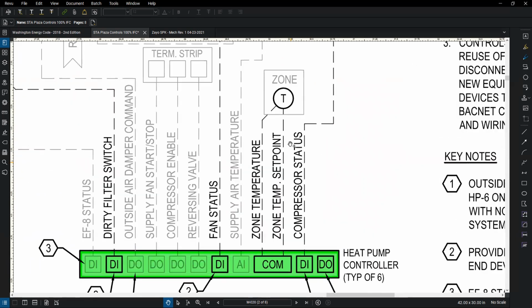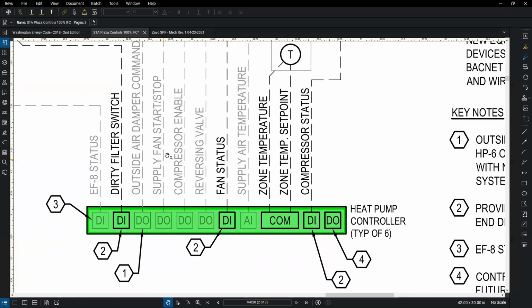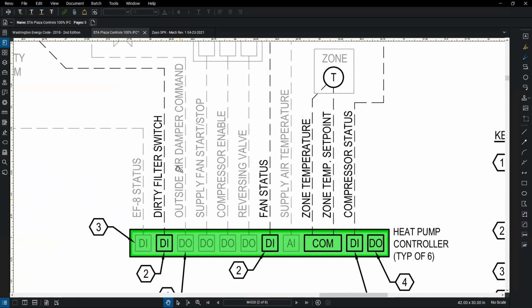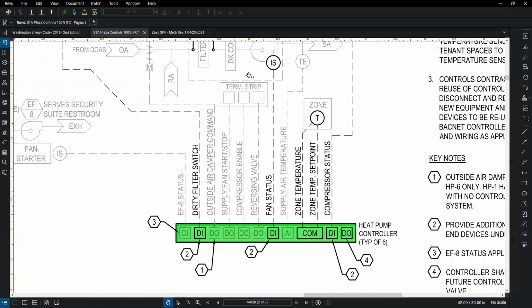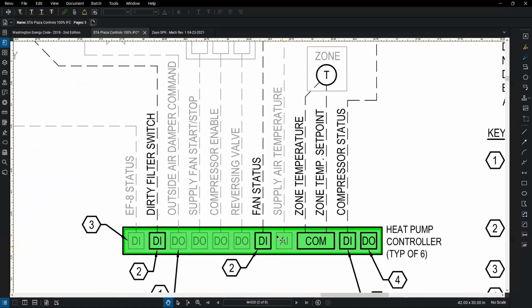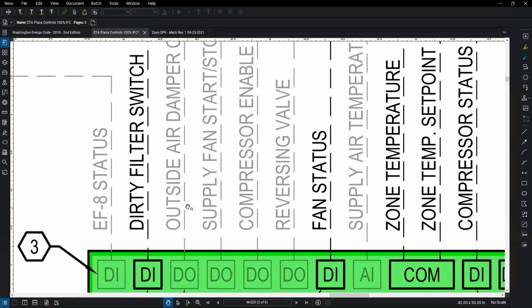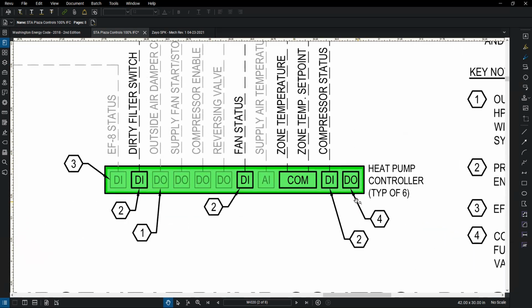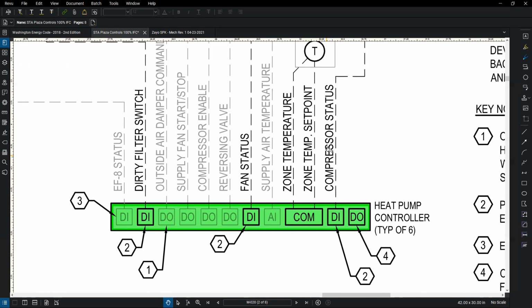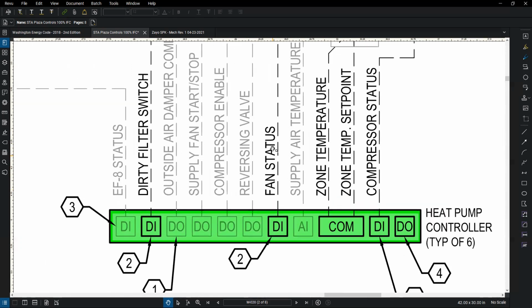So I won't cover everything, but you have your thermostat. The idea is you just see all kinds of stuff here where we are either sending signals out to tell this equipment what to do, or we're bringing signals back in, like this temperature reading is coming back into the unit as an input. In this case, you might notice some of these are a half tone, so they're kind of grayed out. Those were existing control points that were already there. So our main intent here was to replace this part in green, disconnect all these wires, put in a new controller and reconnect those wires. But on our recommendation, we added these darker control points. So they didn't have a fan status point before, and we added that point as part of this project.